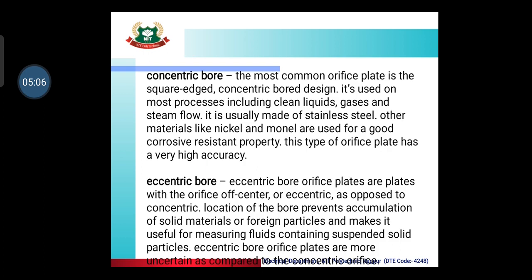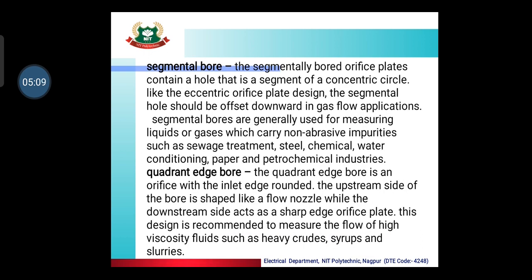The segmental orifice plate has a hole that is a segment of a concentric circle. Like the eccentric orifice plate design, the segmental hole should be offset downwards in gas flow applications. The fourth type is the quadrant edge bore orifice plate. The quadrant edge bore is an orifice with the inlet edge rounded — the upstream side of the bore is shaped like a flow nozzle while the downstream side acts as a sharp edge orifice plate. This design is recommended to measure the flow of high viscosity fluids such as heavy crudes and slurries.